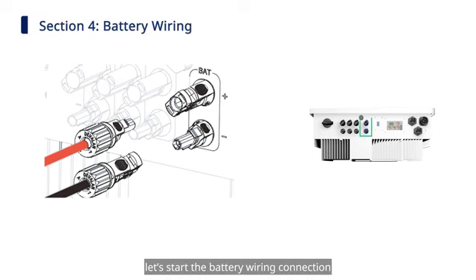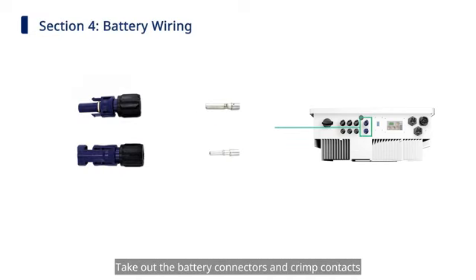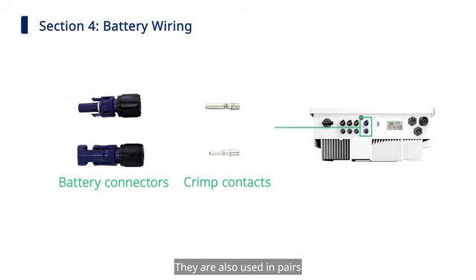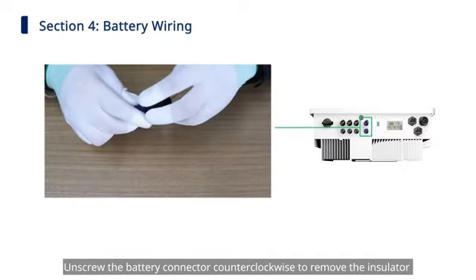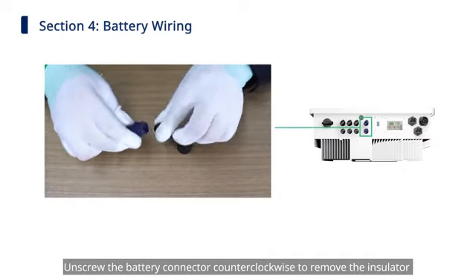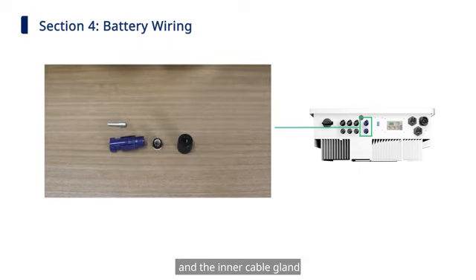Next, let's start the battery wiring connection. Take out the battery connectors and crimp contacts. They are also used in pairs. Unscrew the battery connector counterclockwise to remove the insulator and the inner cable gland.